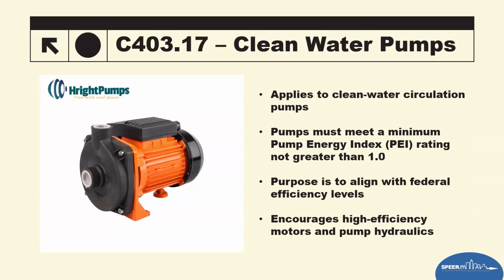And then there is now a specific section for clean water pumps. It basically introduces this efficiency in the 2024 code, where these basically circulate water without particular content, like not wastewater, not processed fluids, it's what's considered clean water. The code now requires it to be defined as a PEI value of less than 1 to ensure they operate efficiently. So this closes a gap, where these pumps were previously exempt or had less regulation.